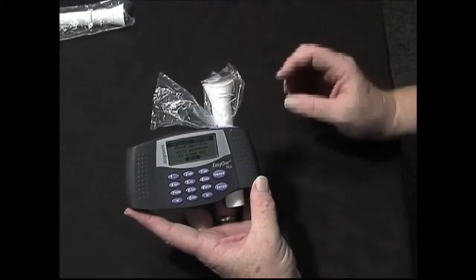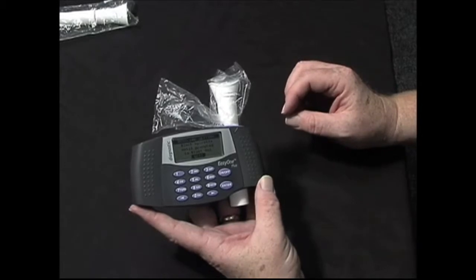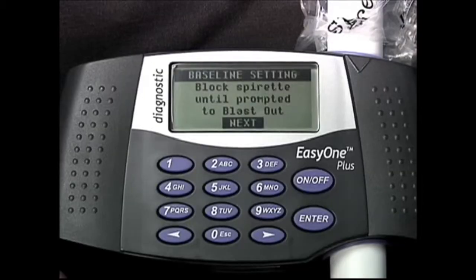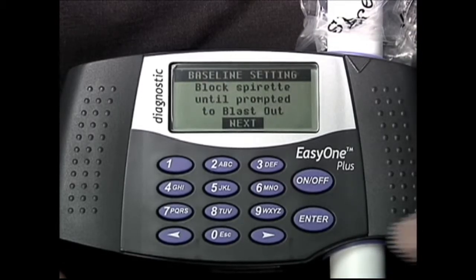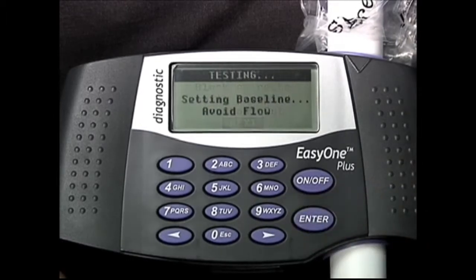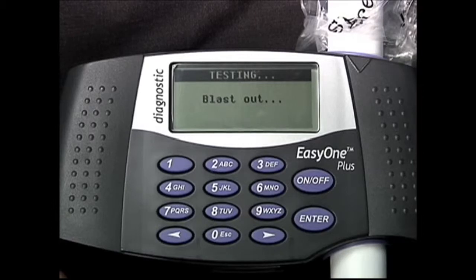Leave the plastic cover in place to make sure that you're blocking any airflow. Once the spirette has been inserted correctly, make sure that you leave the cover on top of it and set the baseline flow. You'll be instructed to block the spirette, that's what the cover is for, and then press Enter to continue. Once it's set the baseline flow, you're ready to do the test.